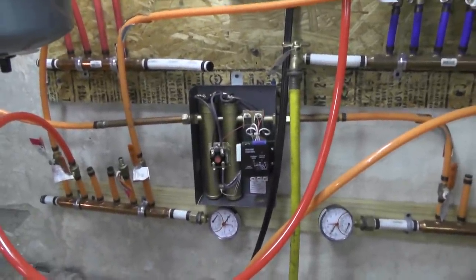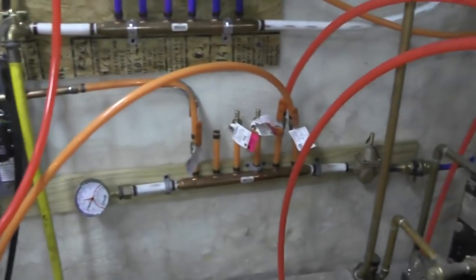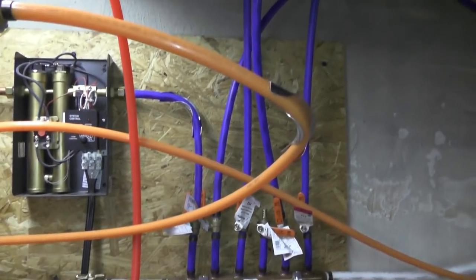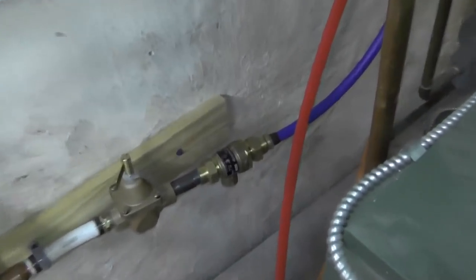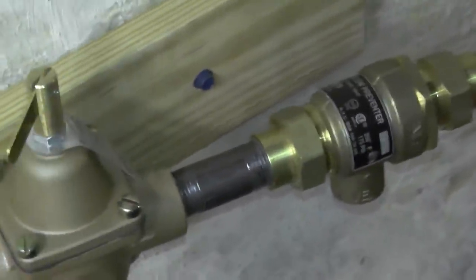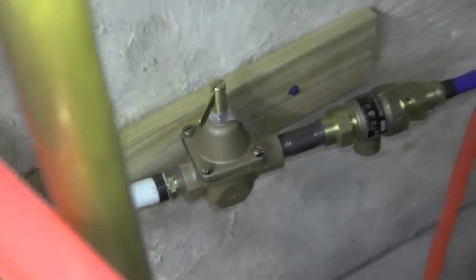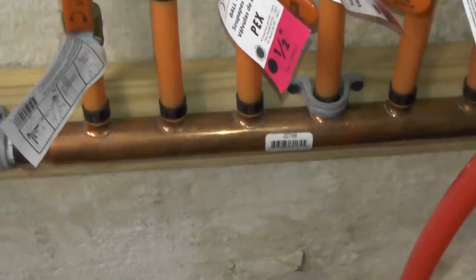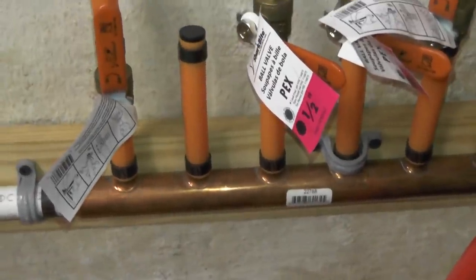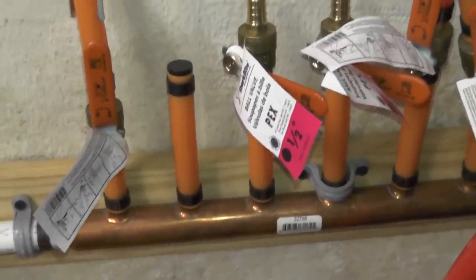So from my cold potable water I just took one line and looped it up and around and that's coming into first backflow preventer and then that's piped over to a fill valve, 15 psi fill valve.